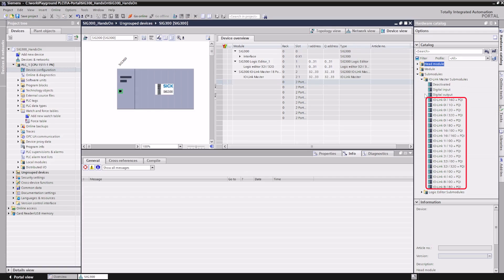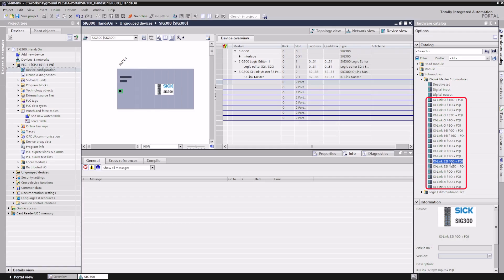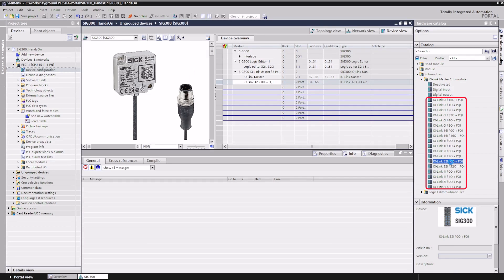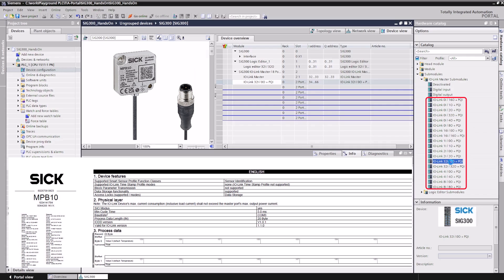When selecting an IO-Link module, please ensure that the process data of the connected device fits into the respective module. In this example, we connect a SICK MPB10 IO-Link multi-physics sensor to master port S1. As specified in the operating instructions, the sensor supplies 20 bytes of process data input.